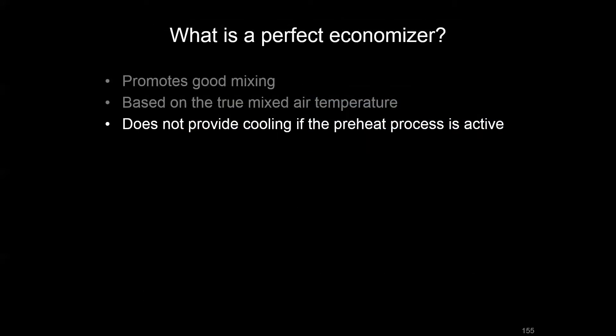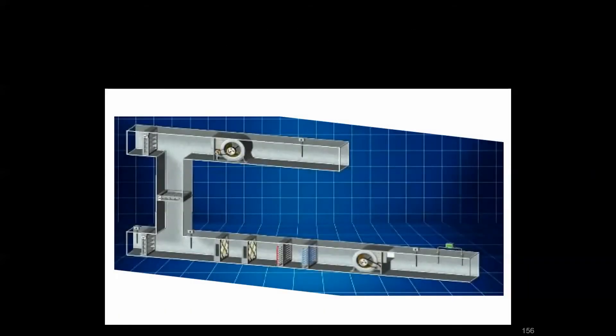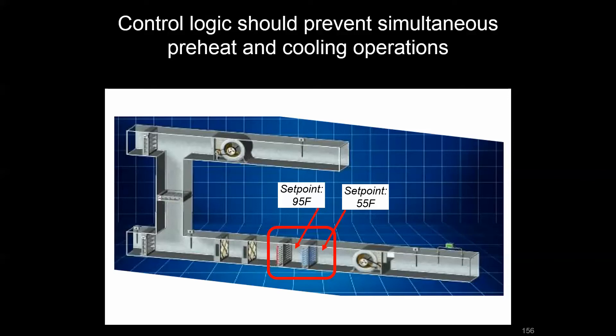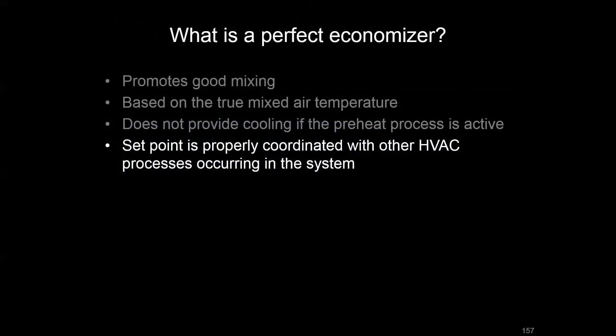We'd also want to make sure that a preheat coil and a cooling coil aren't fighting each other. In this air handler, we might have a preheat coil set point of 95 degrees and a cooling coil set point of 55 degrees. We need control logic that tells the preheat coil to pursue 95 under specific conditions and the cooling coil to target 55 under separate conditions. Watch out for competing control loops.